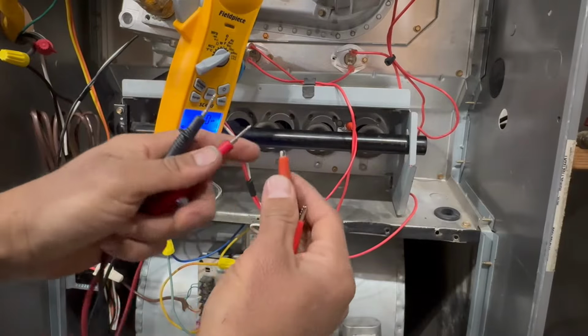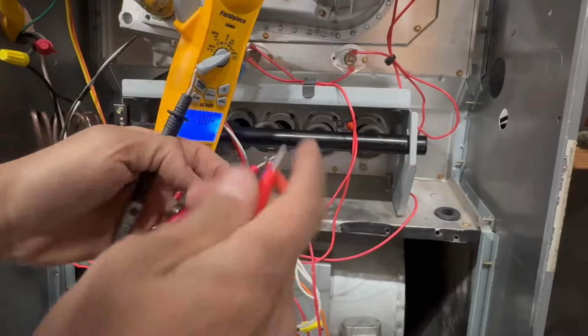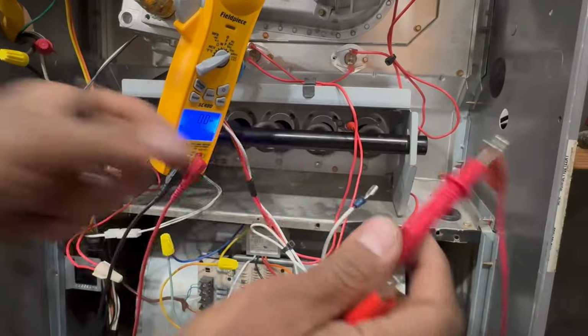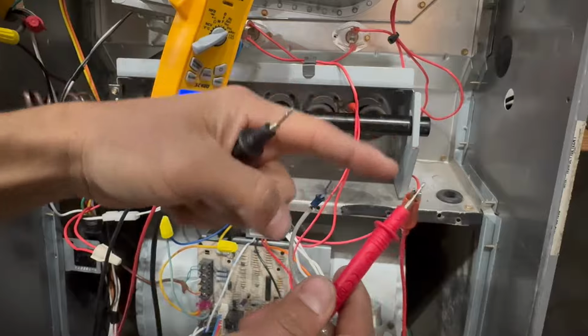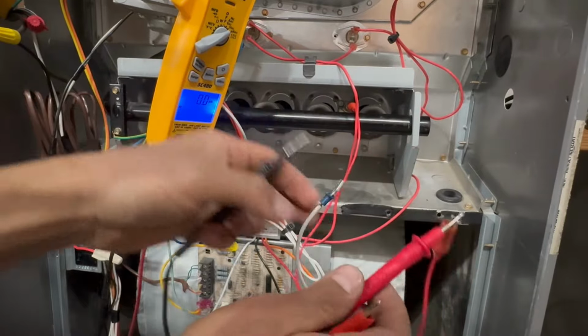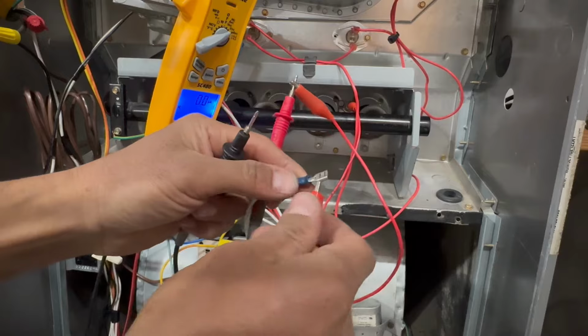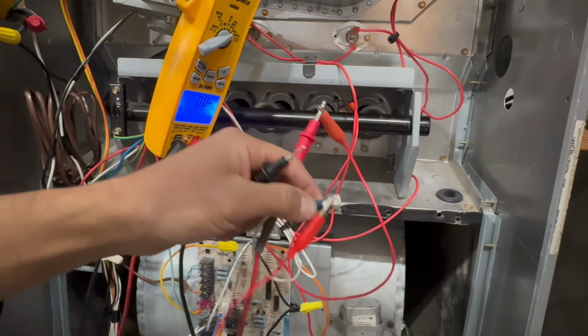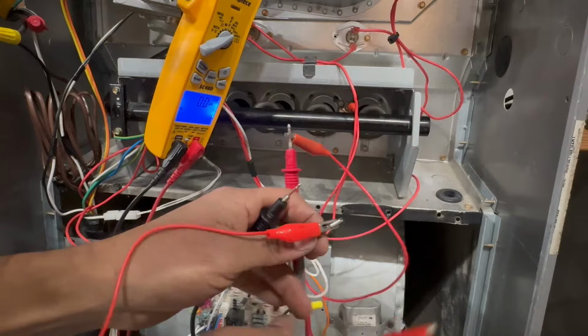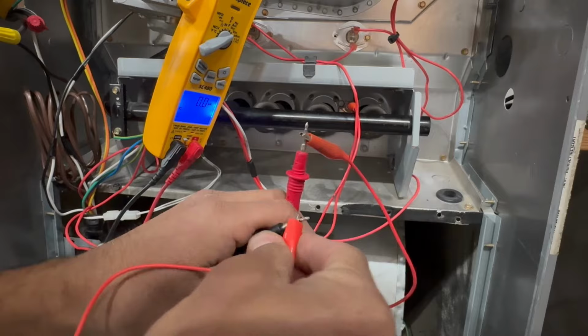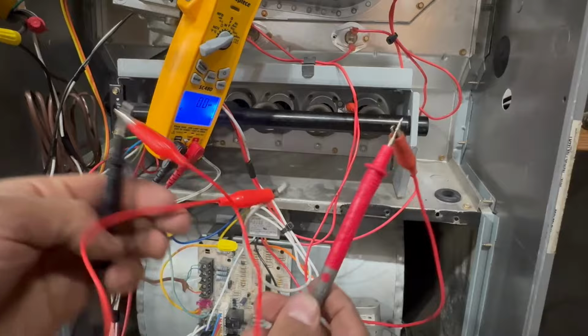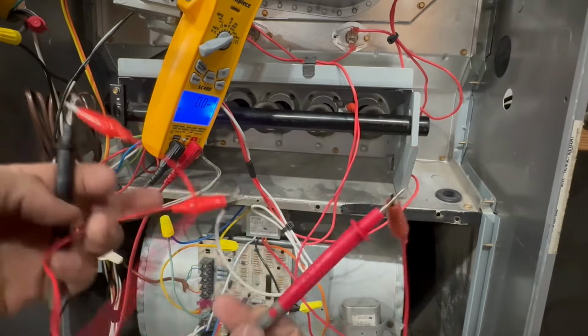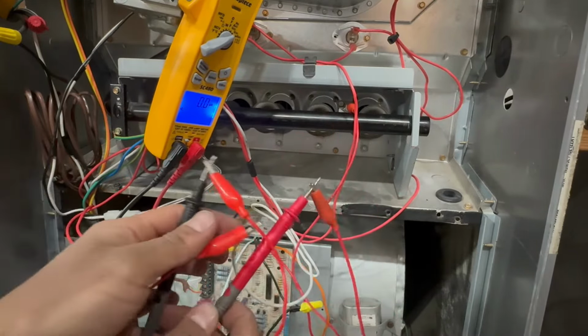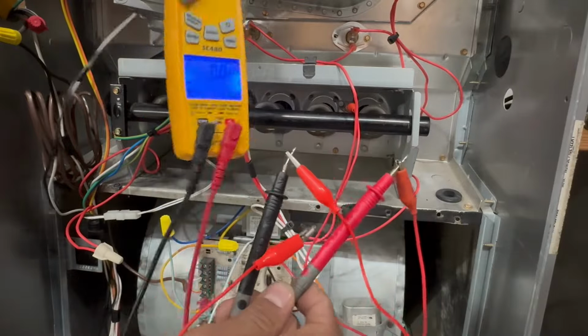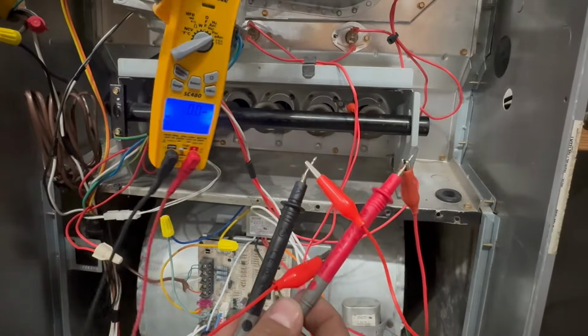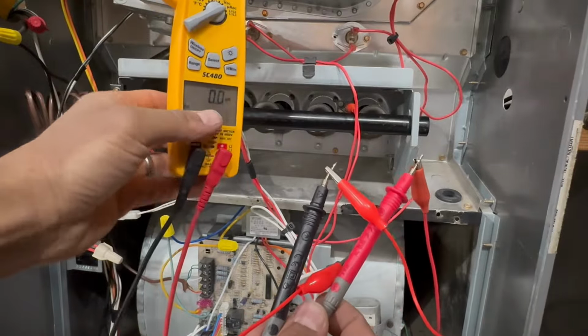Let's go ahead and put it right here on one. Then the other lead alligator clip goes from here to where the flame sensor is. The other one goes to the wire that I pulled out, the black one here. All right, it's done. That's all I did. You see? Wire to the lead, and flame sensor to the lead, and I have it on microamps. Let's see if you guys can see this. You see it's at 0 right now.